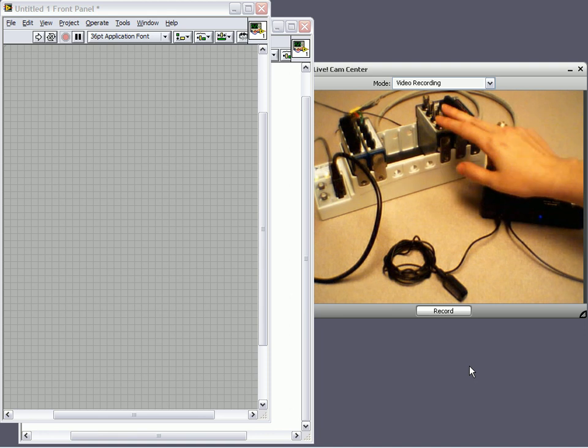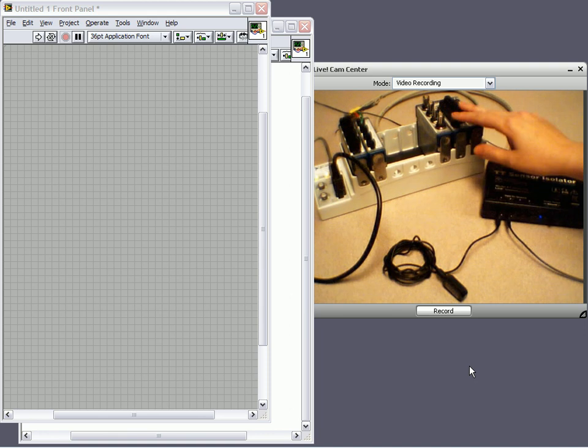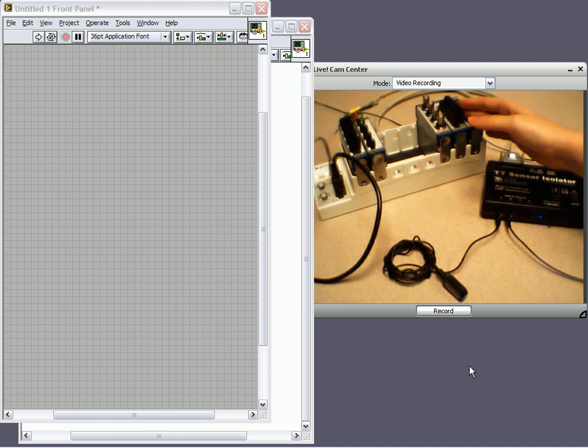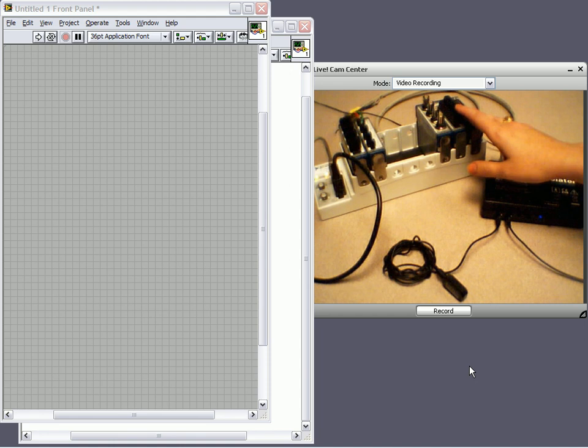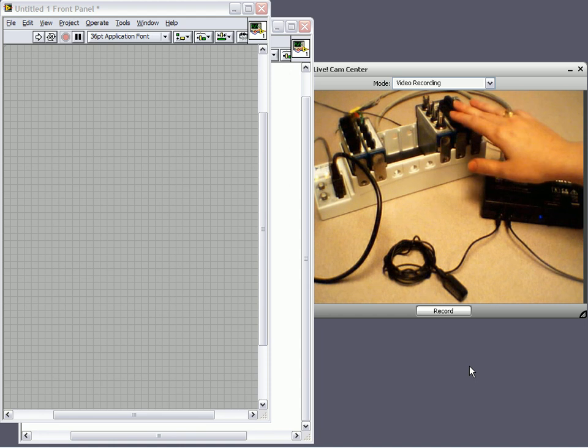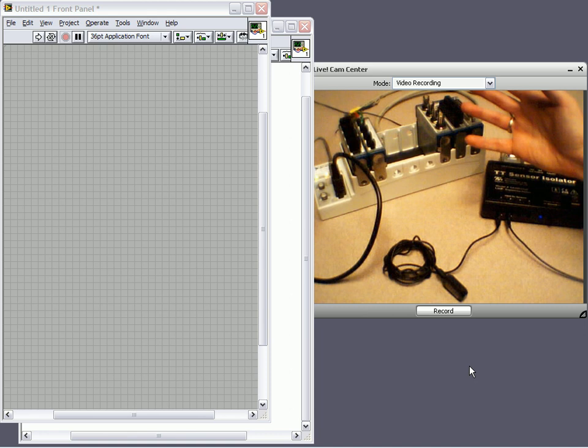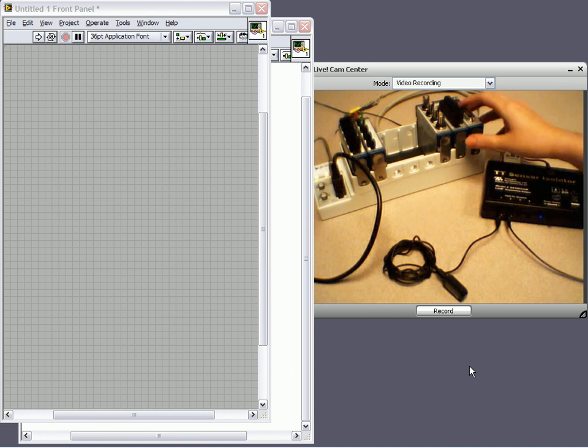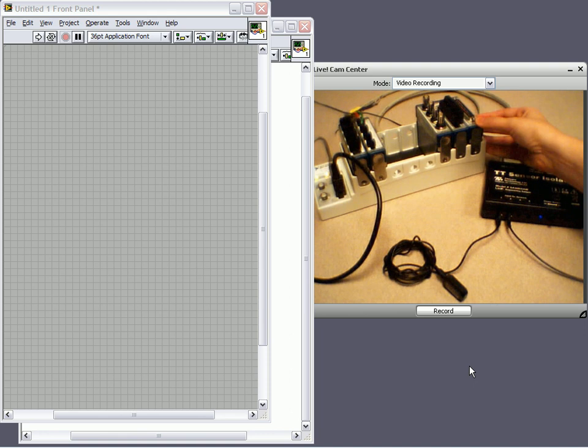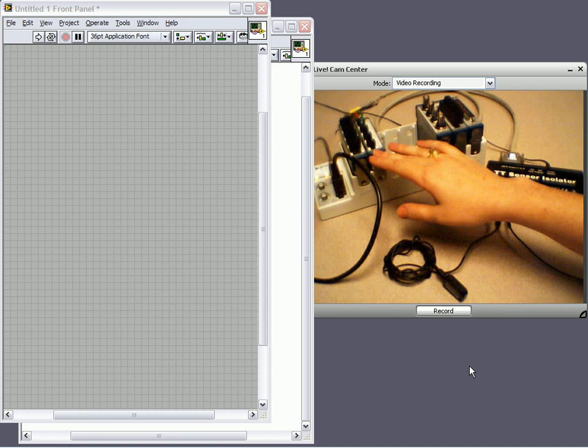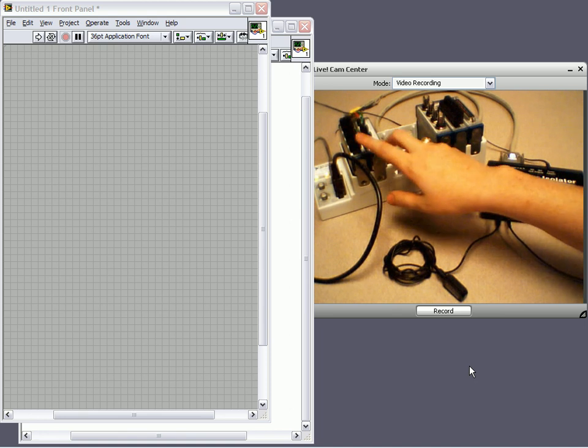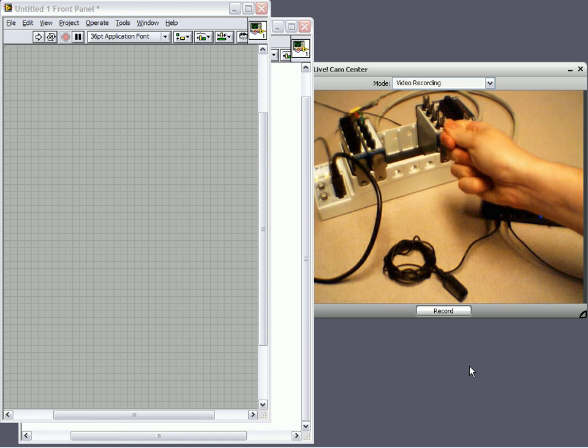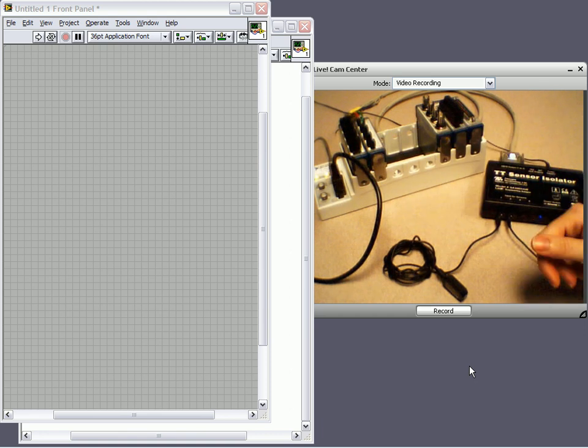So here I've got the 9274, the 9263 analog output module, in case I'd like to generate or simulate an EEG signal, maybe from a file that's been previously recorded. I can output this and connect it to an input to run tests. And here I've got the 9205 32-channel analog input module, and this is if I have a high channel count application. The 9234 and the 9239 only have 4 channels of input. The 9219 here is that universal input module that I told you about, capable of acquiring a number of signals.